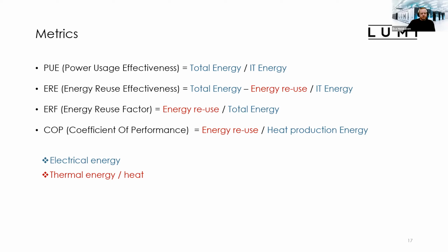So a better measurement for this kind of data center is the ERE value, which is total energy minus energy reuse divided by the IT energy, and this is quite an easy value to compare with the PUE. And this energy reuse factor that I have on this graph indicates how much energy is reused, in percent, compared to the total energy that has been used in the data center.